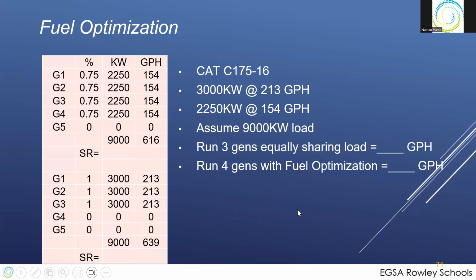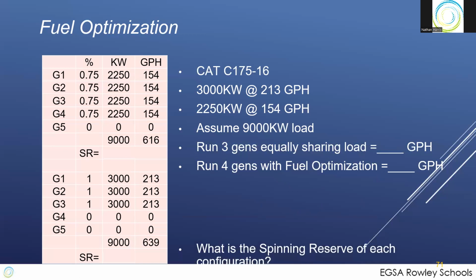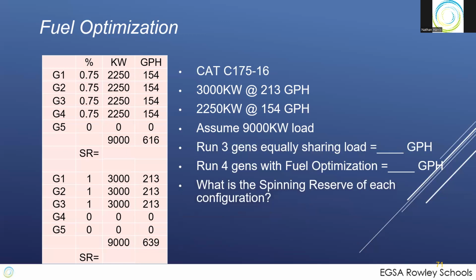What really makes a difference here, what really helps you out, is that if you want to add more load to your system, in this 3-gen system you have no spinning reserve left, right? Spinning reserve in that configuration is 0 down here. With this one it is 3,000. So you can add more load to the system without having to start machines. So you're going to increase your running hours, but it's not at full power, so that helps you with wear and tear a little bit. You're going to have to start and stop more machines at this point. So there are definite advantages to fuel optimization.